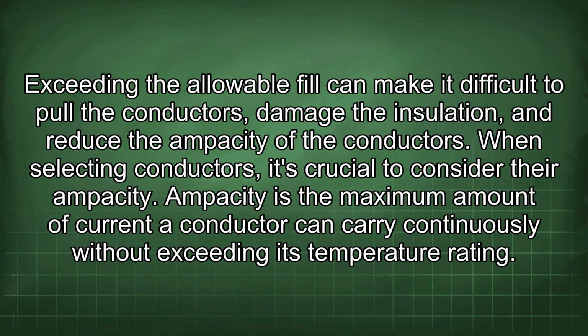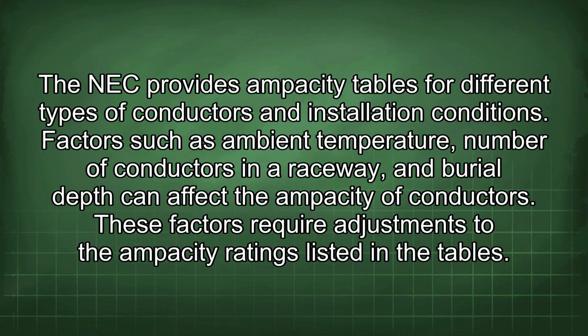When selecting conductors, it's crucial to consider their ampacity. Ampacity is the maximum amount of current a conductor can carry continuously without exceeding its temperature rating. The NEC provides ampacity tables for different types of conductors and installation conditions. Factors such as ambient temperature, number of conductors in a raceway, and burial depth can affect the ampacity of conductors. These factors require adjustments to the ampacity ratings listed in the tables.